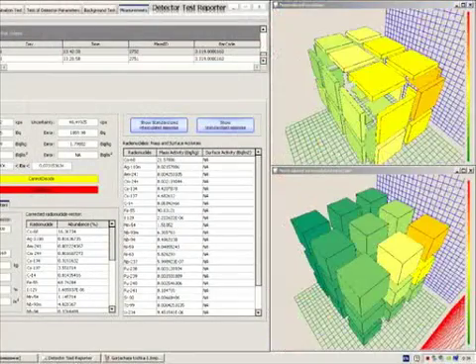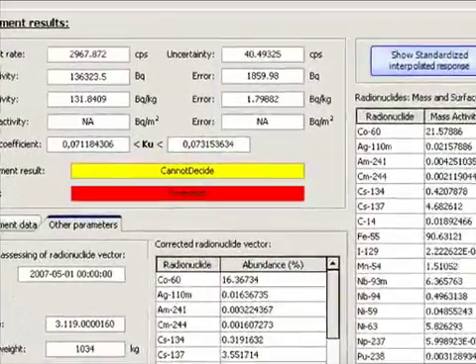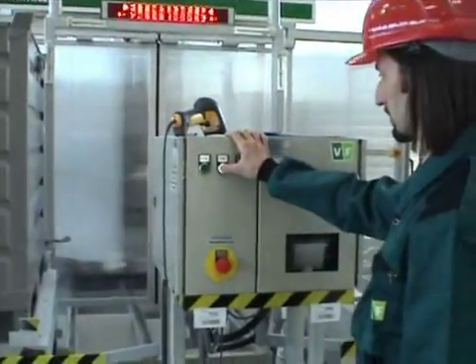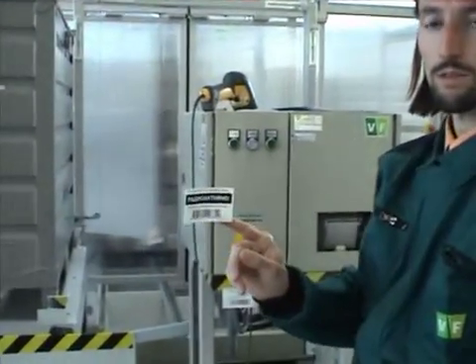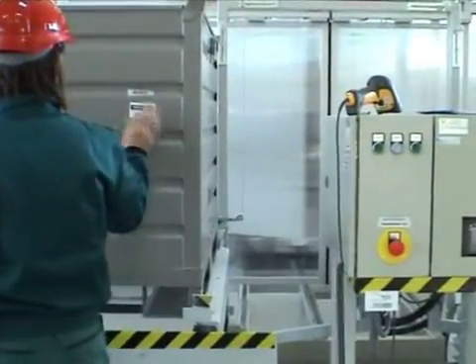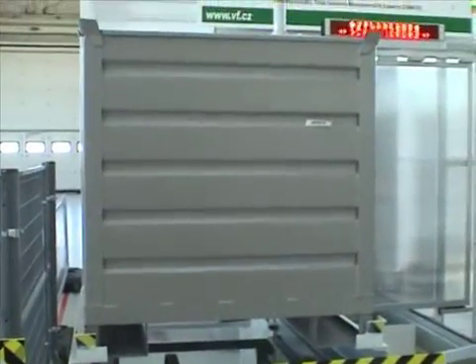If the display reads radioactive, this means that, based on the results of calculations, either the specific activity of the waste is above the free release levels or hot spots have been discovered in the container that exceed the permitted level. Such waste is not permitted to be released. Based on the measurement results, a self-adhesive label is printed out, reading either within the free release levels or radioactive, and attached to the tested waste container.